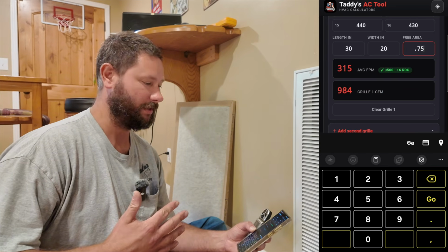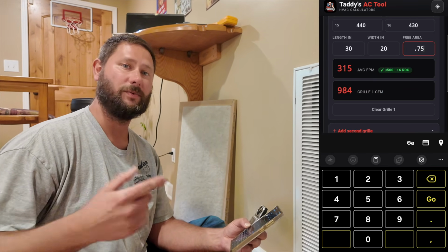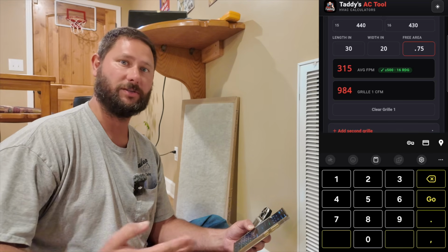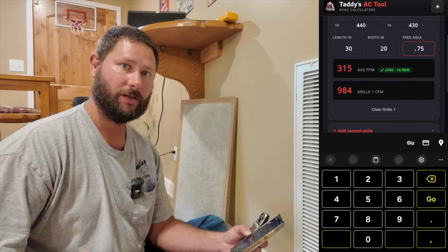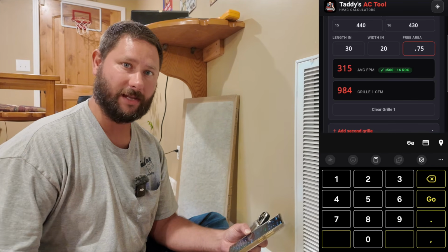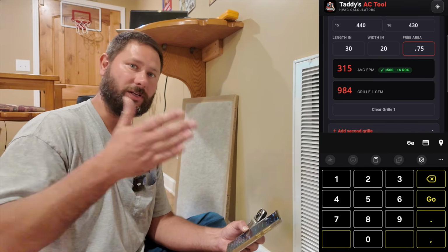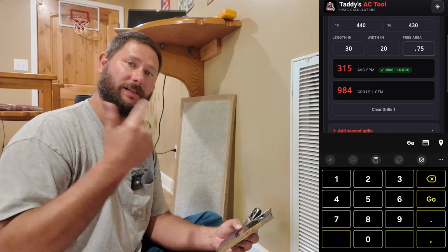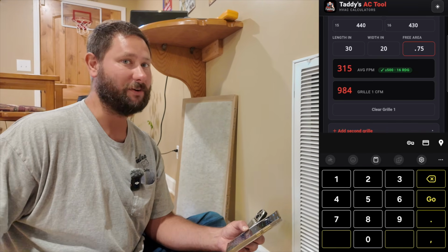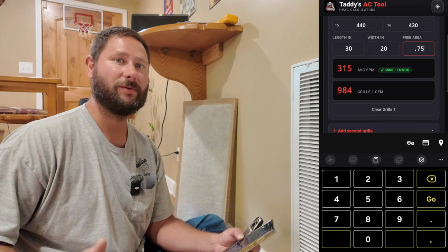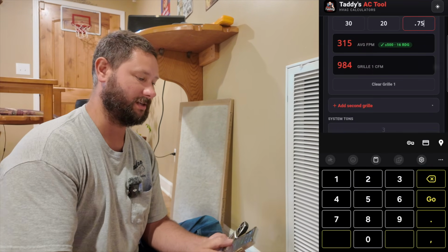That's not good. Now, one thing you wanna do is if you have a 2-stage unit, that means you've got more than one stage for cooling, you need to make sure it's on second stage, unless you're checking each individual stage. This unit is 2-stage. So we could be in first stage, but I'm pretty sure we're in second stage. So there could be something wrong.